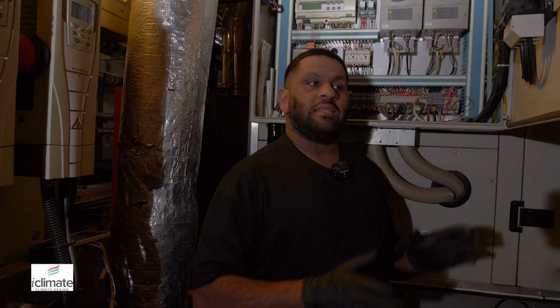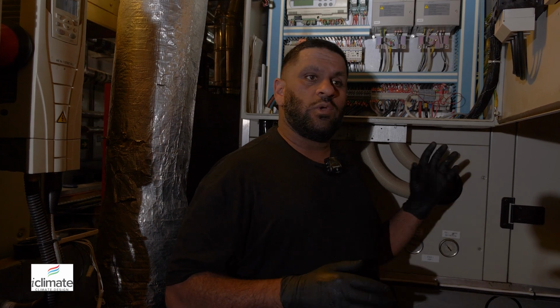C. Water chillers need to maintain a delta T of 5 to 6 degrees to ensure that the superheat on the evaporator is going to be perfect and the chiller is within its flow range, right? So when you do a chiller maintenance, you also need to look at the flow rates across the heat exchanger, and also obviously the usual servicing that you do for a refrigeration plant to make sure that all coils are clear. But with chillers, you need to be a bit more thorough. And this is what I used to do 15 years ago for all the large commercial companies like Honeywell and the Emirates Stadium, looking after chillers all the way up to 1 megawatt and centrifugal. So this is just like a walk in the park for me.